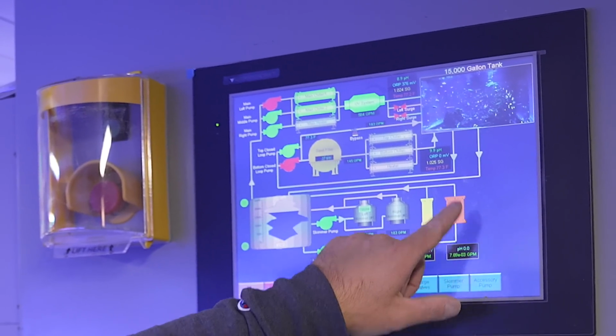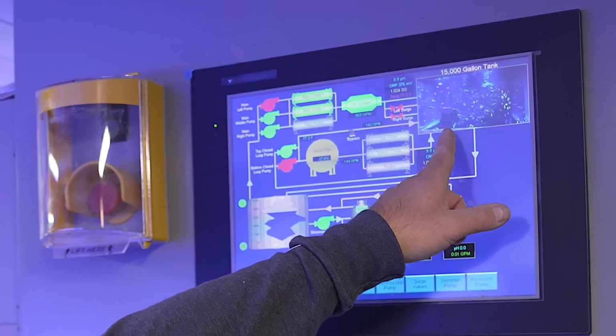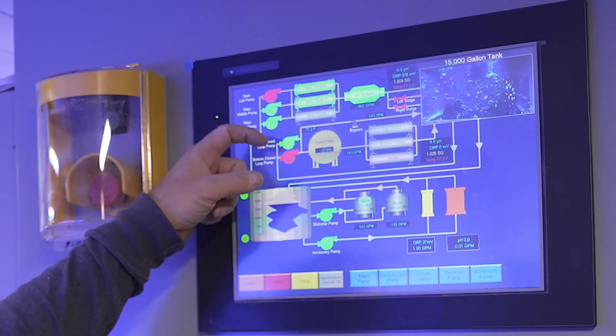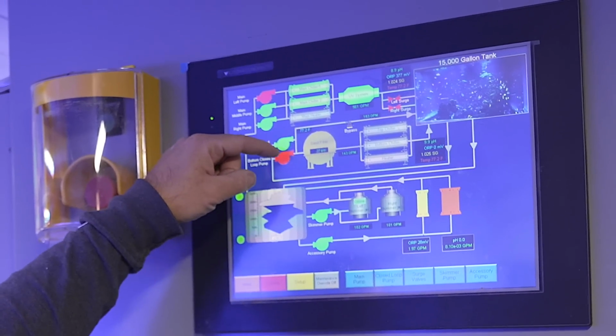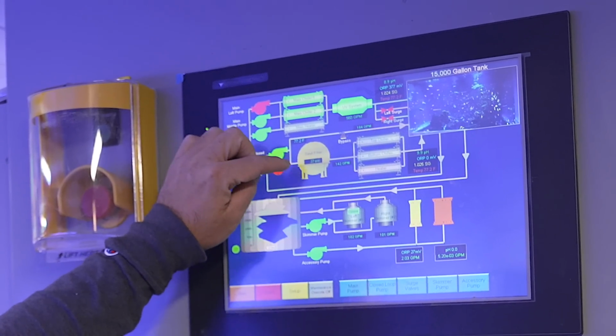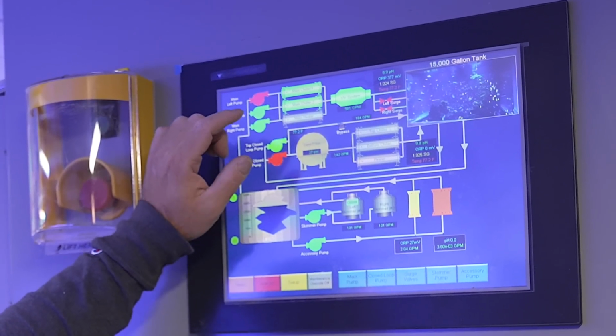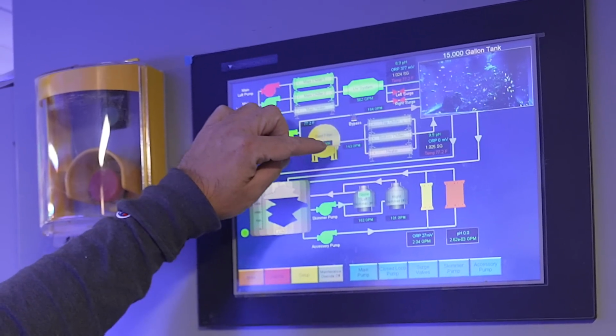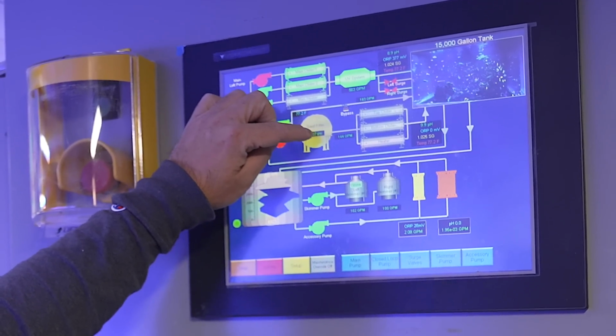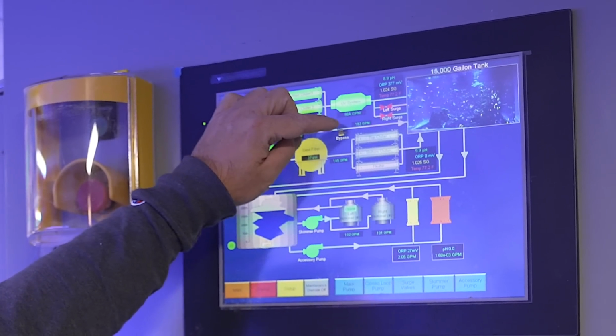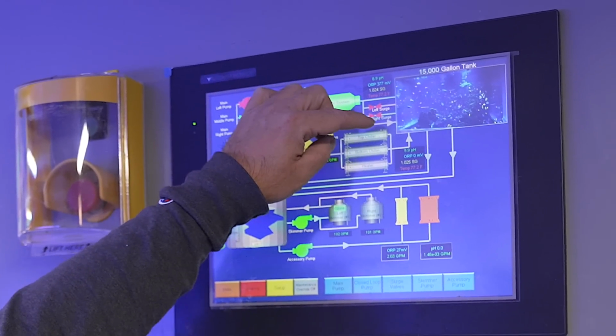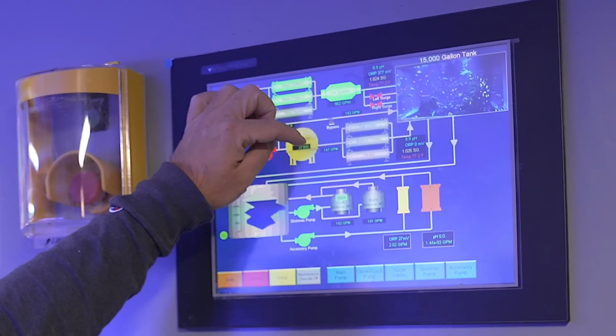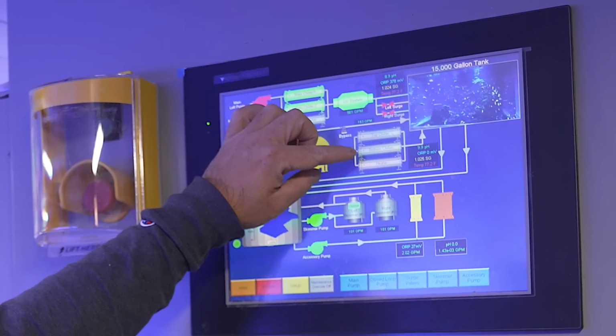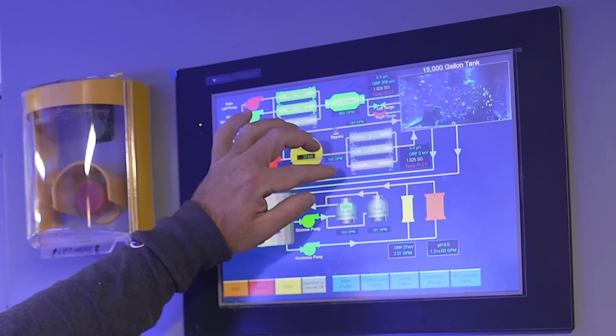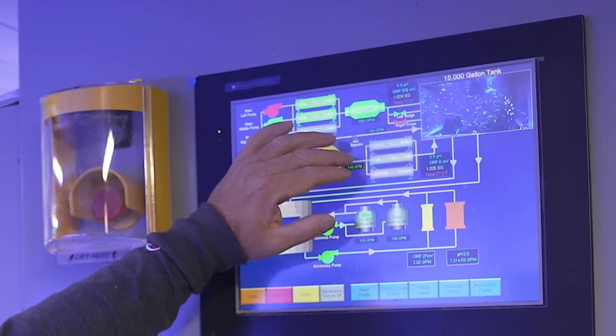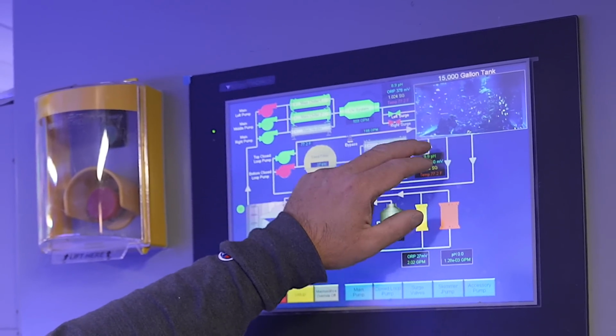We then also have the closed loop, which is drawing water from the tank back into a pump. We have one running and the backup there. We are then flowing through the sand filter, which has 27 psi of pressure in it, and we backwash it when it gets to approximately 30. So there's 144 gallons a minute going through the sand filter. The whole closed loop is running 182 right now. We're running a side stream with some water bypassing around the sand filter. The water that is filtered through the sand filter then goes through two chillers and a heater, none of which are on at this current moment. All that water reconverges and returns back to the tank.